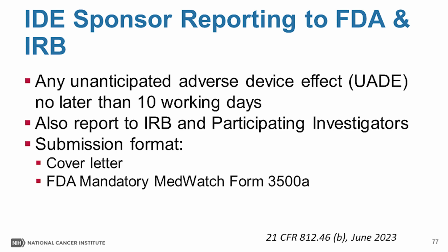And then the sponsor who's conducting the evaluation of the unanticipated adverse device effect will report the results of their evaluation to the FDA and to all of the reviewing IRBs and participating investigators within 10 working days after the sponsor first receives notice of the device effect.